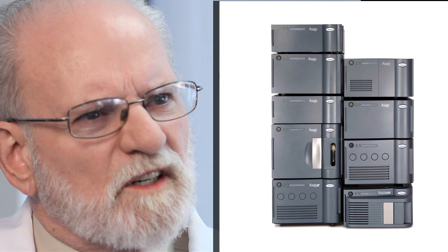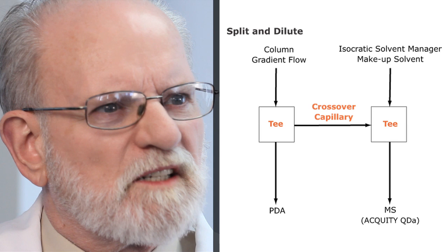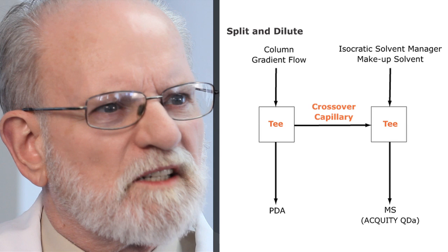The column flow is delivered to the two detectors through the isocratic solvent manager. A split and dilute technique ensures that both detectors are in their respective linear ranges.